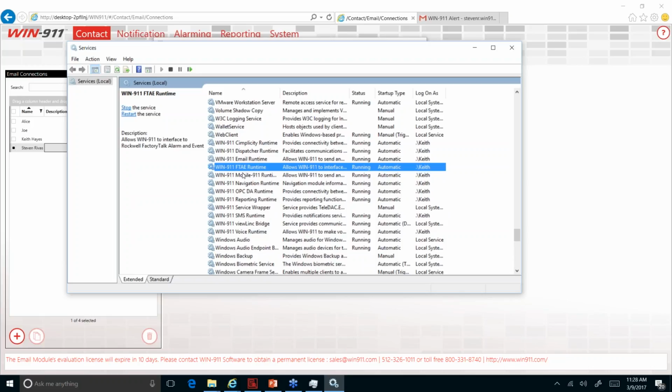Can the InTouch connector be run as a service using the service wrapper like V7? No, I don't believe InTouch will run as a service. You have to run as an application in order to connect, due to the Windows session that everything's running in. If WindowViewer is running in one Windows session, then our runtime needs to be running in the same session to make that happen.